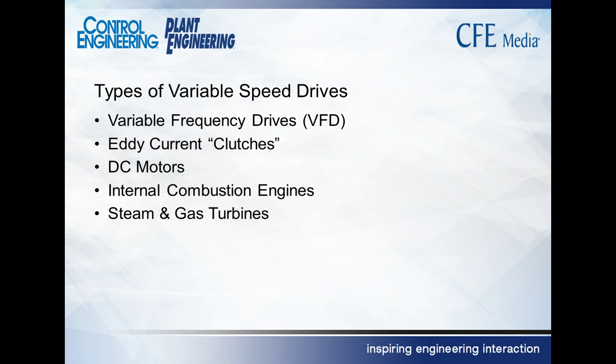I've used care here to talk about variable speed drives. Many people consider VFD instead of VSD as a variable speed drive, but that's only one of the different types. It's worth mentioning there's different types of variable speed drives. Certainly varying the frequency on an AC motor will change its speed, a very common, easy retrofit on an existing installation. But there's other options as well.